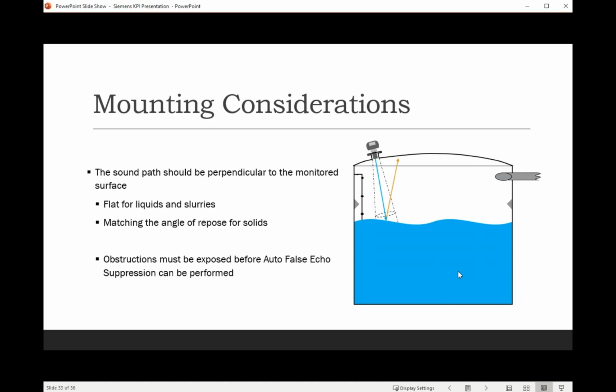Also, another thing to consider is with the ultrasonic transducer, you want it to be perpendicular with the surface that you're monitoring. So with liquids, with wavy, turbulent surfaces like lift stations or anything, you want to have it pretty much perpendicular, pretty much flat, shooting straight directly down at the media in order to give you the best signal return coming back to the transducer. If you have a solids application using ultrasonic, you want to have it pointed at the angle of repose. So then if there are any obstructions in there, we can use auto false echo suppression, where we map out the ladder or the rungs or anything along those lines.